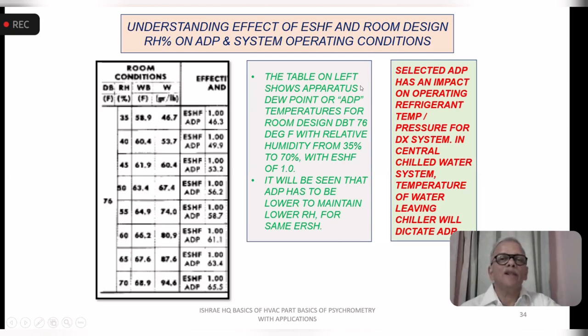So the table on the left is showing the apparatus dew point, or ADP temperature, for this room design condition. It will be seen that the ADP has to be lower to maintain the lower RH, for the same effective room sensible heat. So if you have the humidity as, say, 60%, which is here, the ADP required is 61.1.